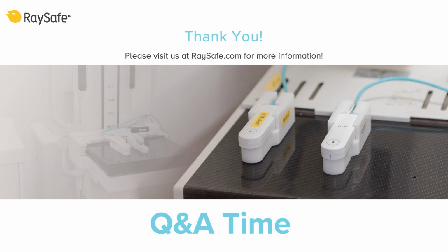Why don't high dose rates appear in the calibration certificates? Well, when we designed the product, we did a lot of tests, of course. And we actually saw that just by adjusting at those calibration points that we have in the certificates, we are able to capture the whole energy range and the whole dynamic range of the meter.